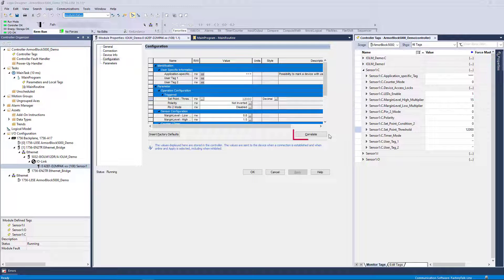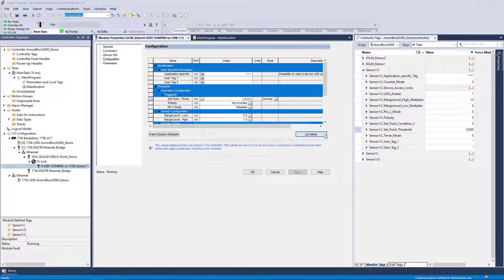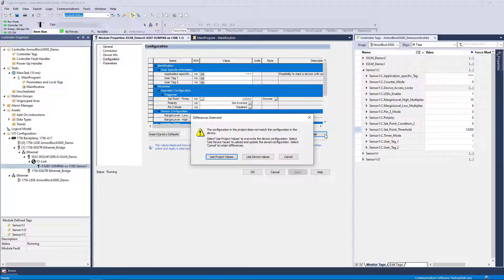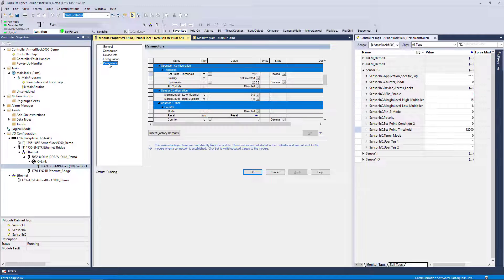If we attempt to correlate at this time, it will alert us that there is a mismatch and we can choose to use the controller or device value if desired. For now, we will cancel this correlation and verify that the value on the Parameters tab has not been updated.